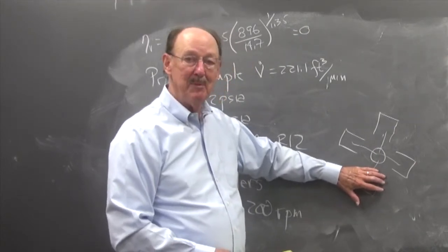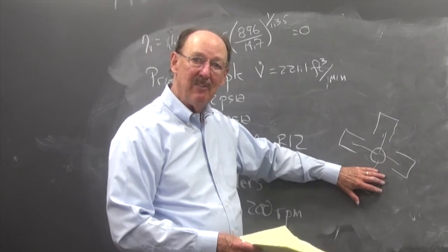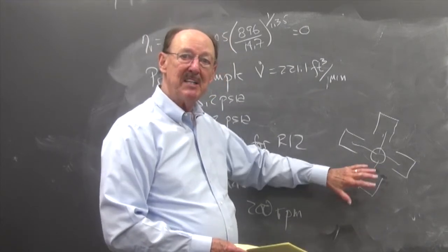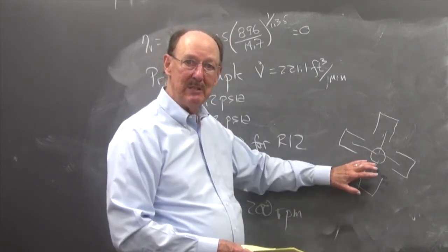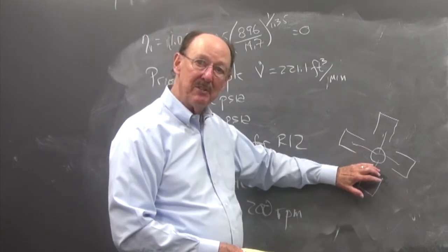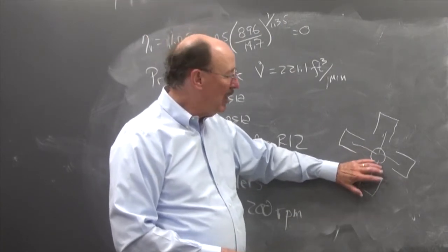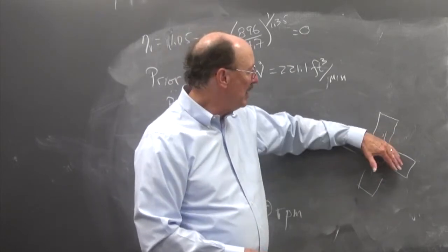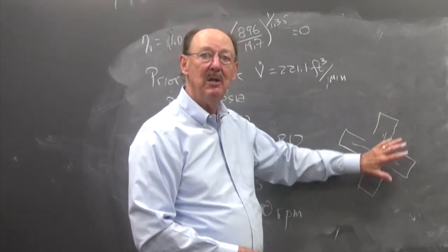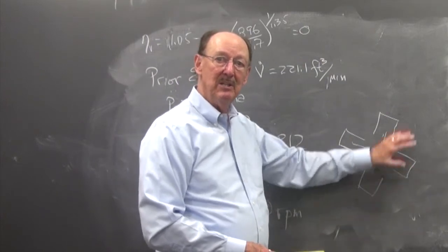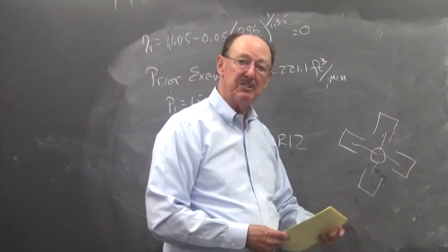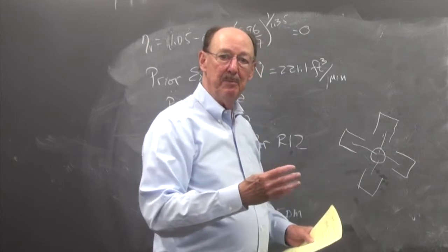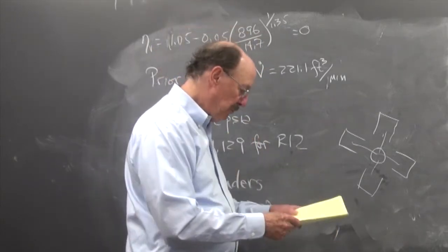Basically you pick up the valves so they no longer work. So as the mass flow rate decreases because your cooling load decreases, you unload your compressor. It also means when you start up again, you're starting up with only 1 piston as the load rather than 4 pistons as the load. So it's a nice design, and the text talks about the unloading of the valves for this.